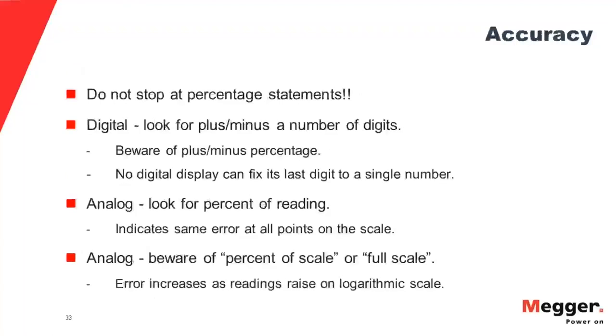Accuracy. The main thing here to look at is 2 points. Make sure that the number of digits is included in the accuracy statement. You will see accuracy statements like plus minus 2%, plus minus 2 digits. No digital instrument can fix the last digit on the scale. It will always jump up and down a little bit, but you don't want it jumping up and down very much. So make sure that your accuracy statement includes the number of digits, because some manufacturers, how should we say, poorly designed equipment will omit that because it's not very good. It may be 6 digits. So make sure that you look for that.